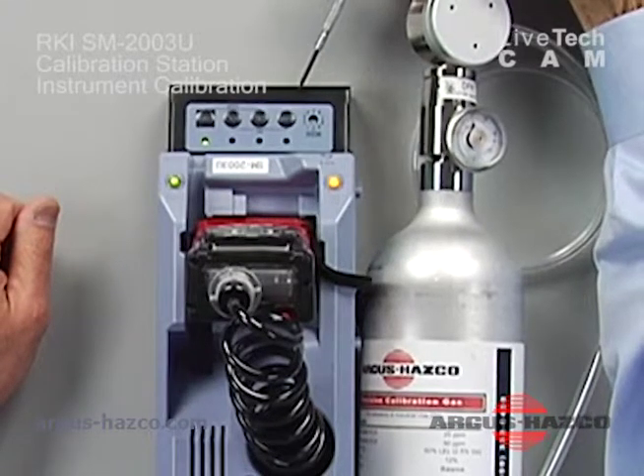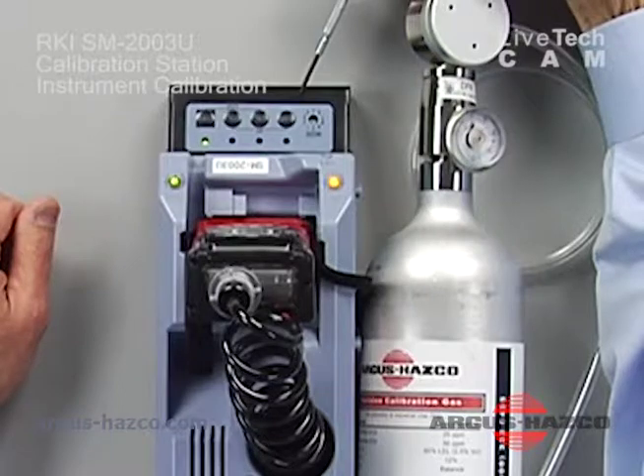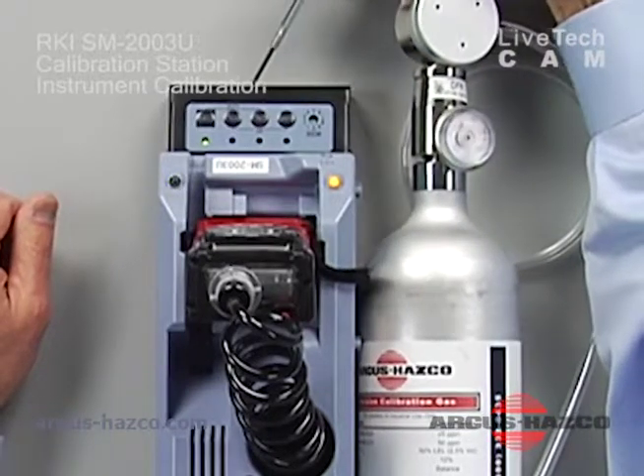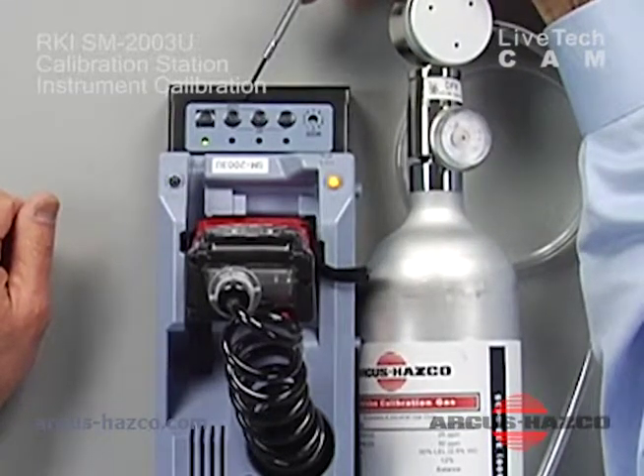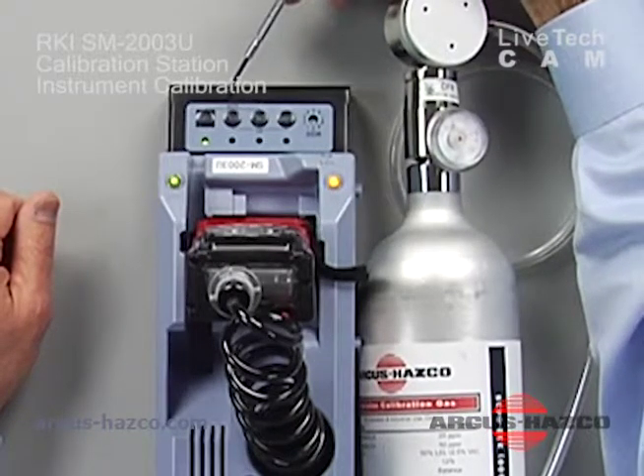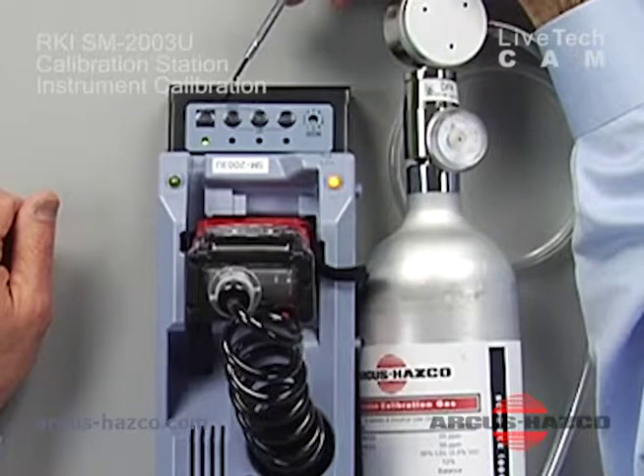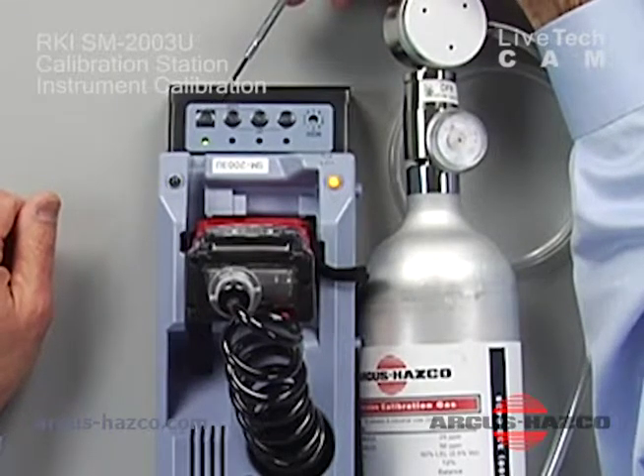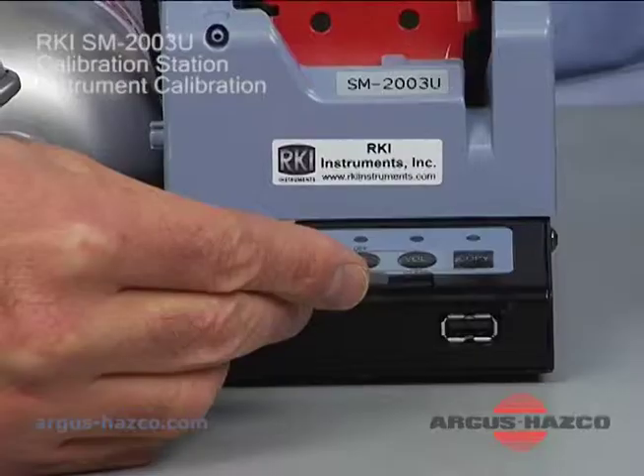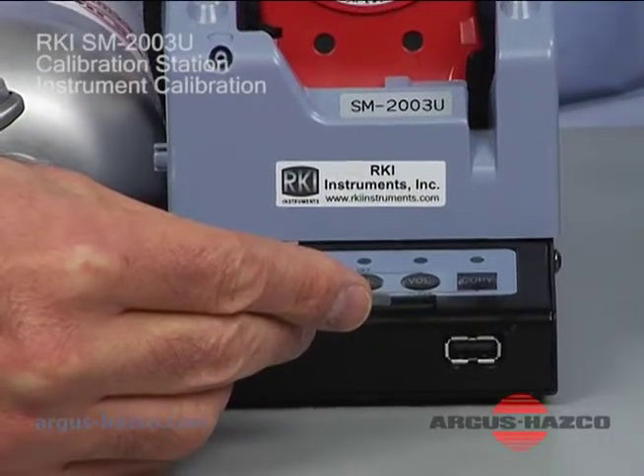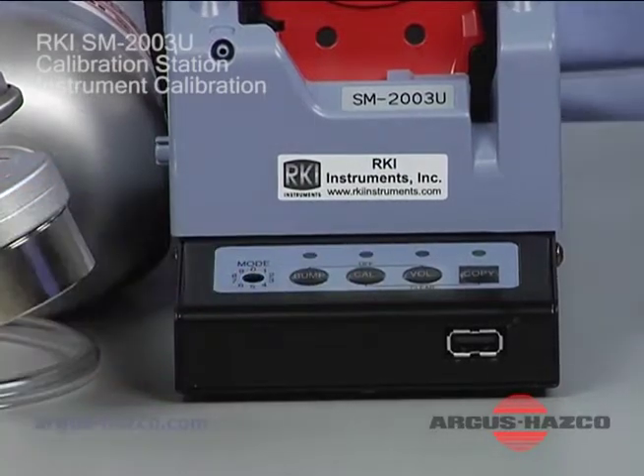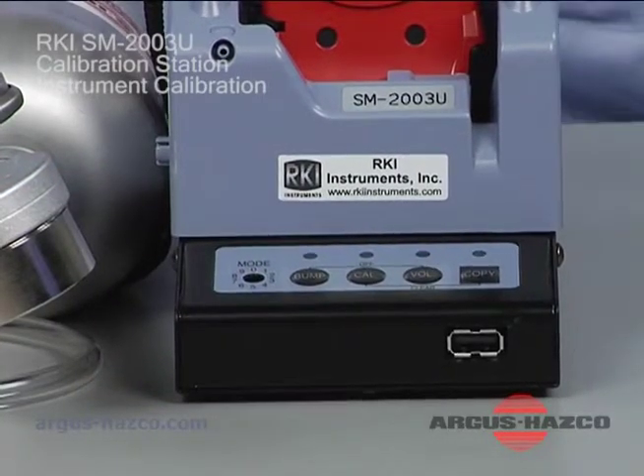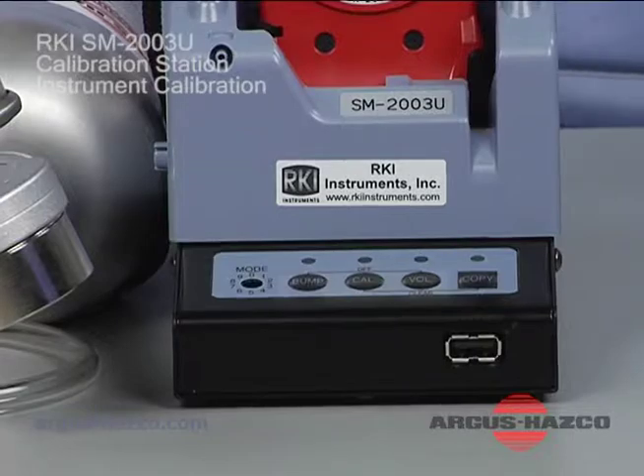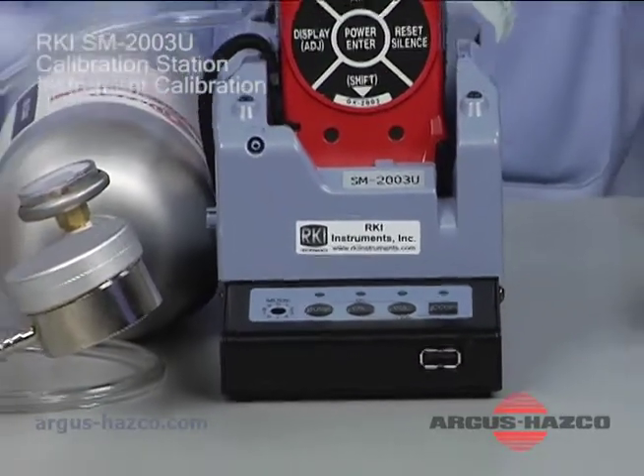Okay? And this is your bump button. This is your cal button, percent by volume button if you had a percent by volume sensor installed in the instrument. And then this is your copy button. You see there's a light above the copy button. I did perform one calibration. If there's a light that shows above the copy button, that indicates that there is information within the standalone calibration station that can then be extracted with the thumb drive.